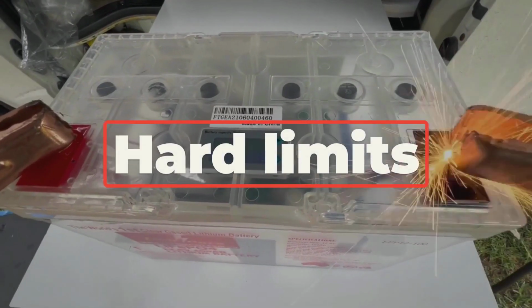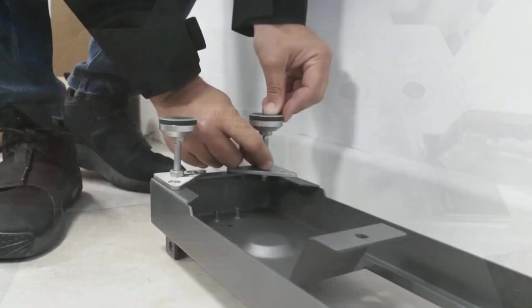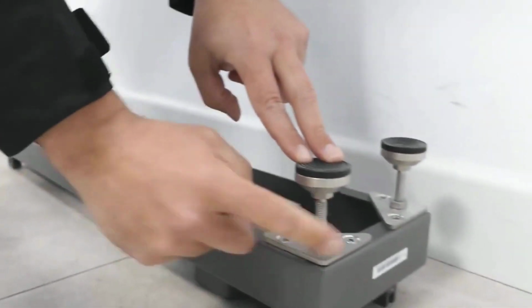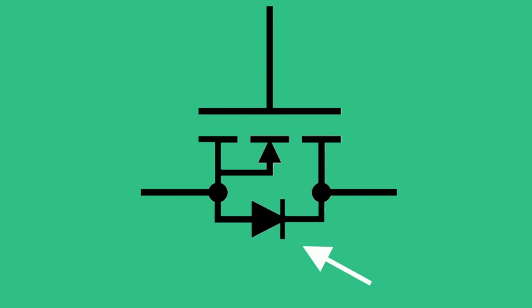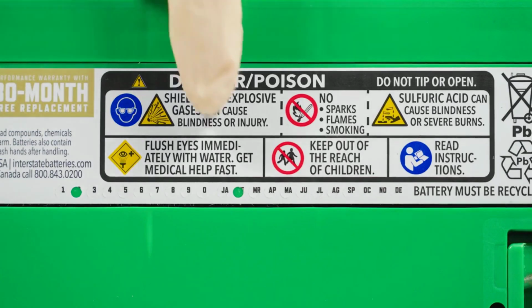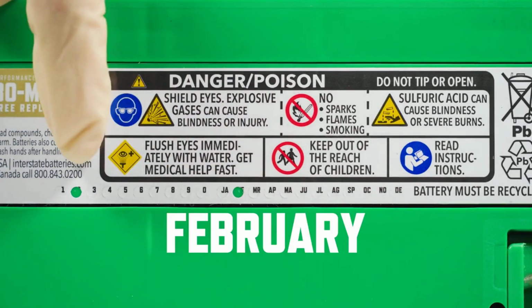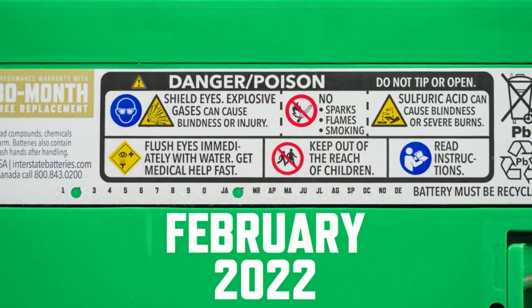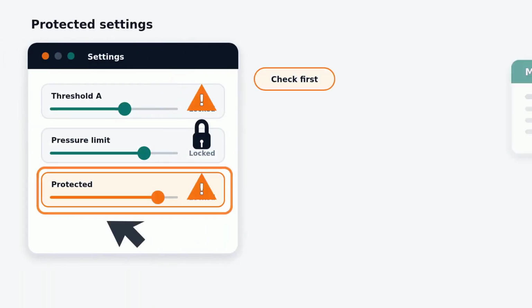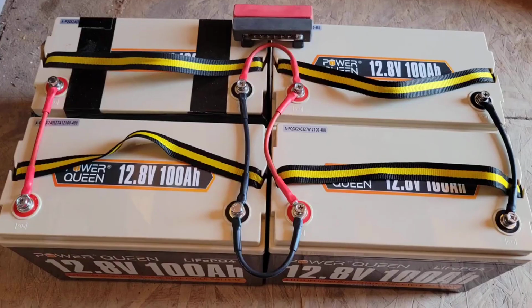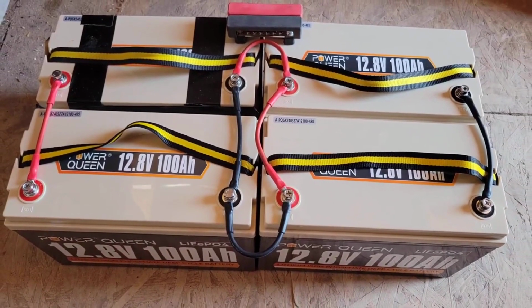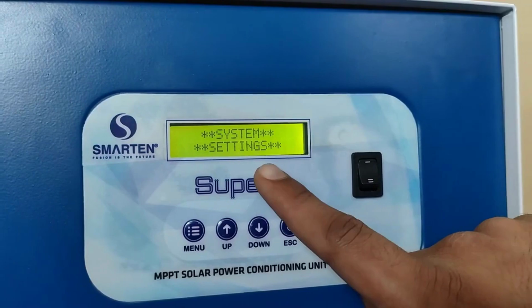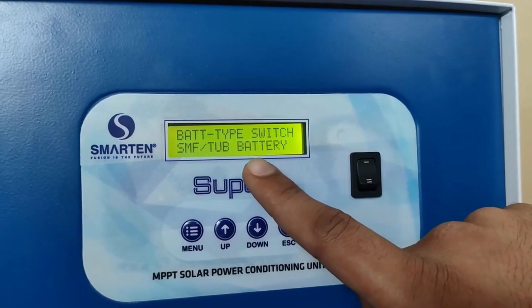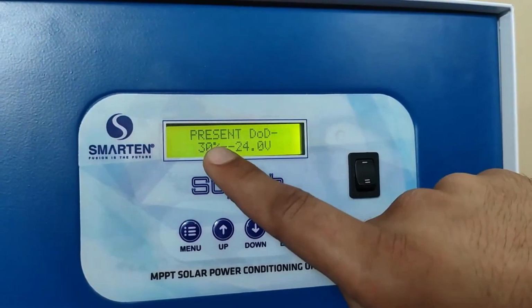There are also hard limits you do not cross. Do not set your inverter cutoff below the battery manufacturer's published minimum discharge voltage. Do not attempt to bypass or override the BMS. Check your manual and your warranty terms before touching any protected threshold, because some systems void coverage the moment you modify those parameters. The setting exists to protect the battery from you. Use it that way. So now you have a number dialed in. Here is how you confirm whether it actually worked.